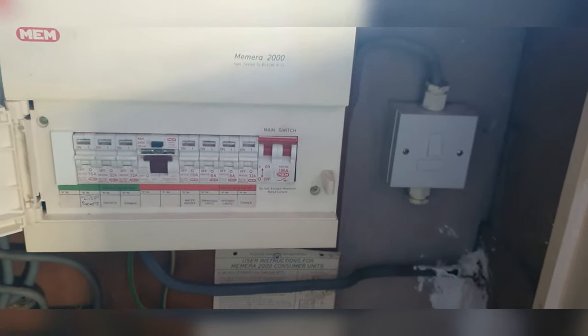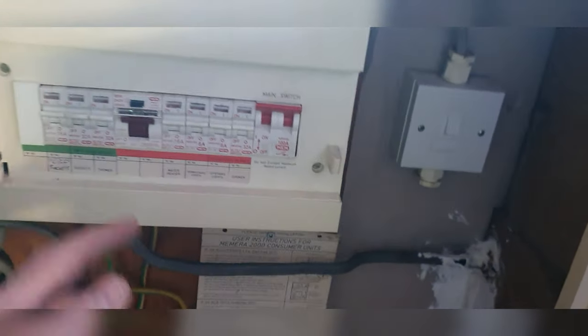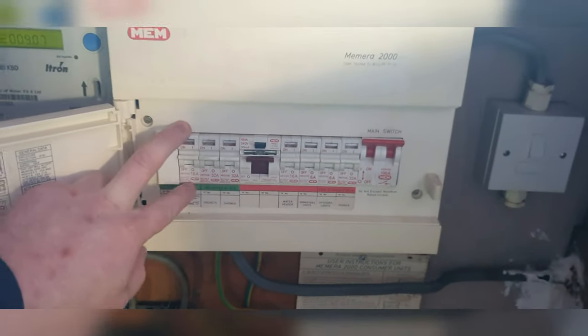So we did the inspection - I'll show you what we're doing. We've got this old MEM board here. We've recommended a board change, that's our recommendation, but the landlord didn't want that. There's no RCD protection on the bathroom lights - I put it on the spare. We can't get anything to fit this side, so just put it on the other side.